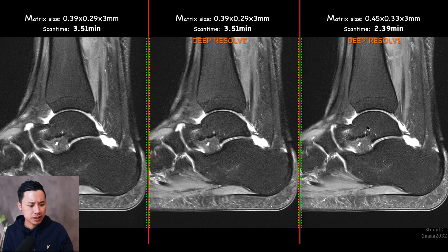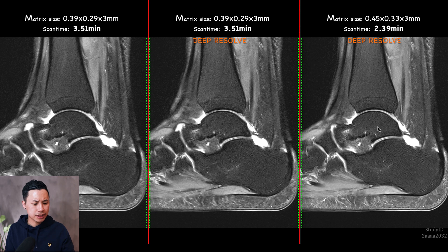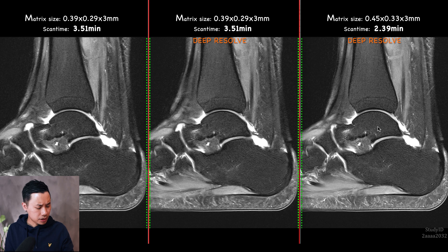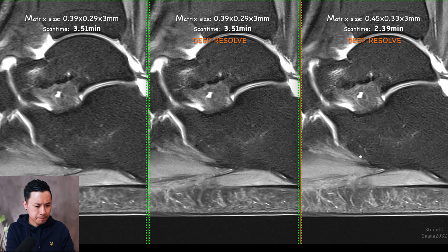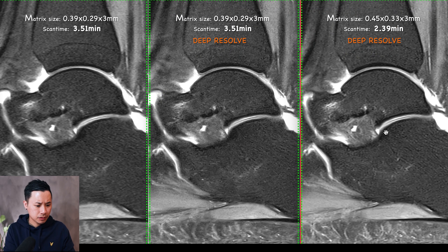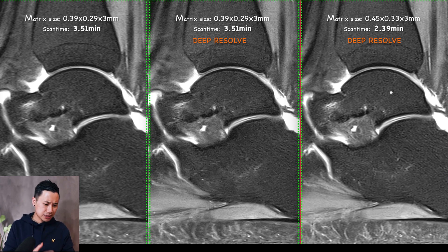The last one has a slightly lower resolution as you can see — the voxel sizes are a little bit bigger — but the scan time is lower of course. So these two: 3 minutes 51 versus 2 minutes 39. Let's check the images. For me, it seems that this shorter scan time with Deep Resolve, with the settings we're using here, looks sharp.